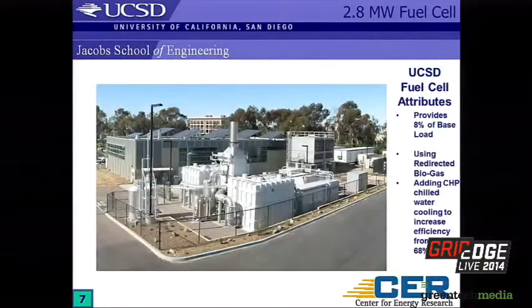We have a project underway right now to add another cycle onto that fuel cell to capture the waste heat. It's an adiabatic absorption chiller that's going to be used to generate more chilled water for air conditioning load. That'll raise the efficiency up to about 68%, which will be one of the most efficient fuel cells of that size in the country.